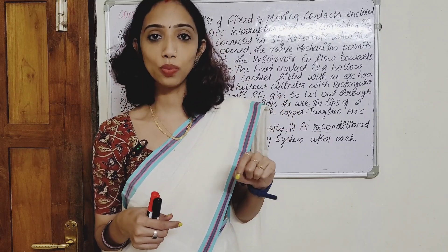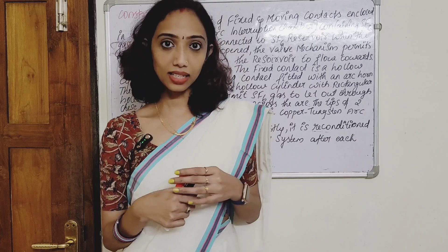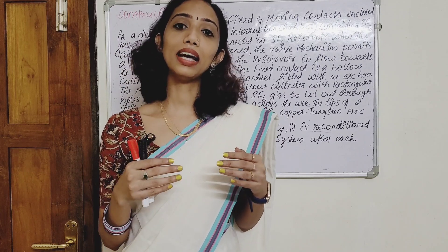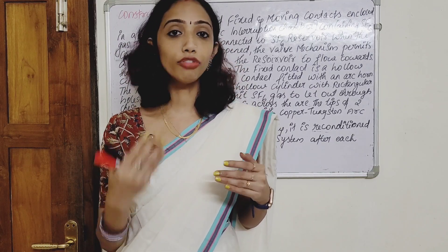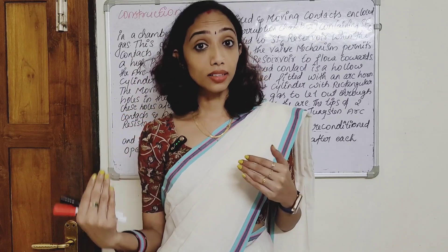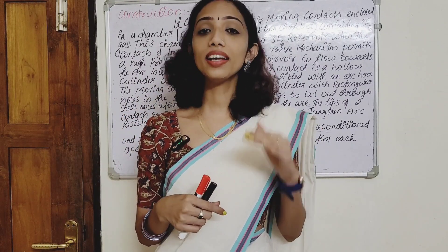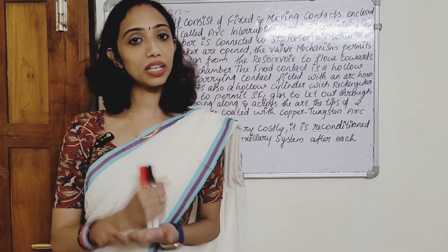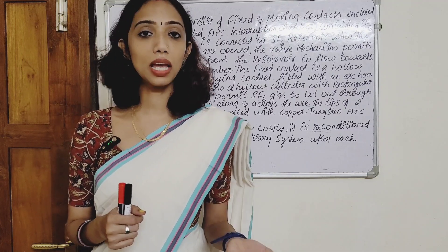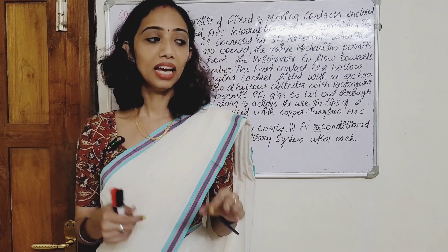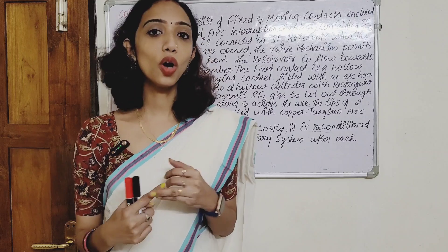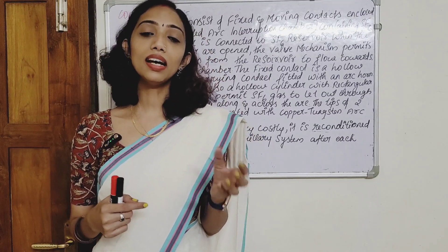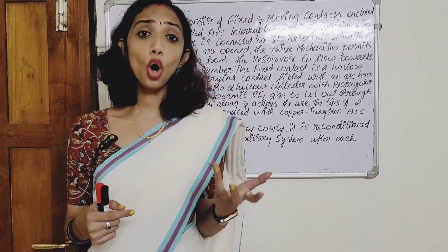The two contacts are housed in what we call an arc interruption chamber. When a short circuit current or high current occurs, the arc interruption takes place inside the arc interruption chamber. The main items in the construction are: the moving contact, fixed contact, and arc interruption chamber. The two contacts are made of copper-tungsten.